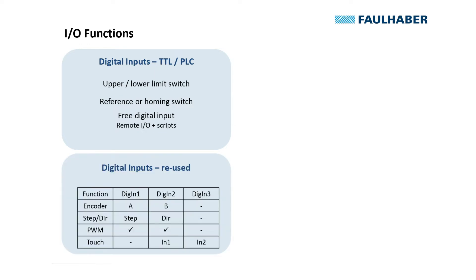Alternatively, they can be reused to connect either an additional incremental encoder or to connect a step-direction interface so that the motion controller can be used like a stepper driver. You can also connect a single PWM input value or reuse the digital inputs as touch inputs to capture a position.